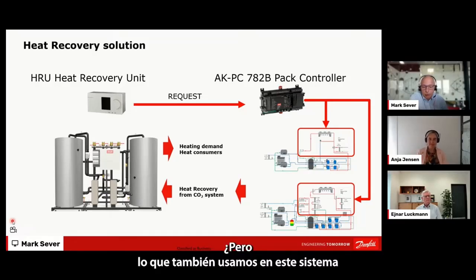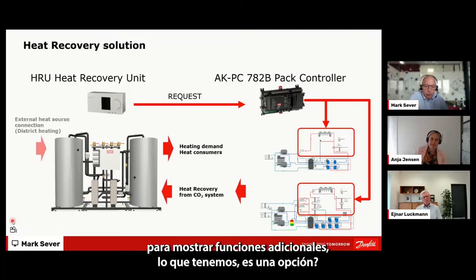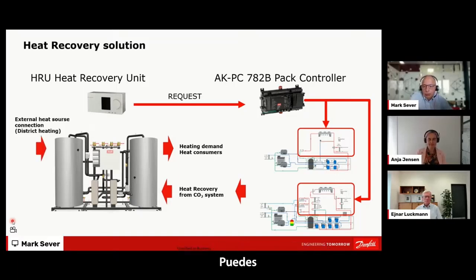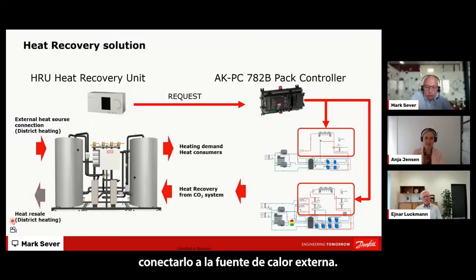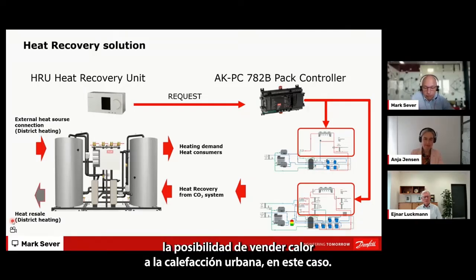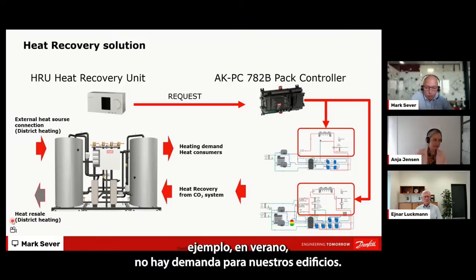But we also wished with this system to show additional features of what we have. It's an option - you can connect it to an external heat source. In our case this is district heating, but we also have the possibility to sell heat back to the district heating. And of course when we have a surplus in heat, for example in summertime, there is no demand on our buildings, but still the refrigeration system will work at higher pressures because of higher ambient temperatures.